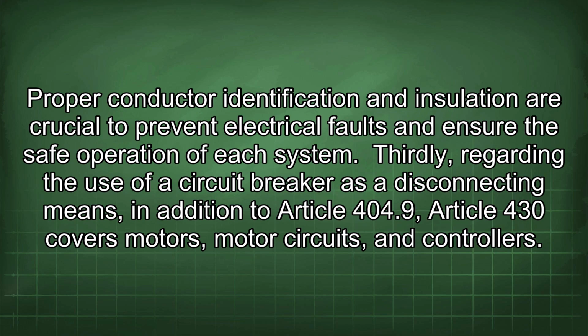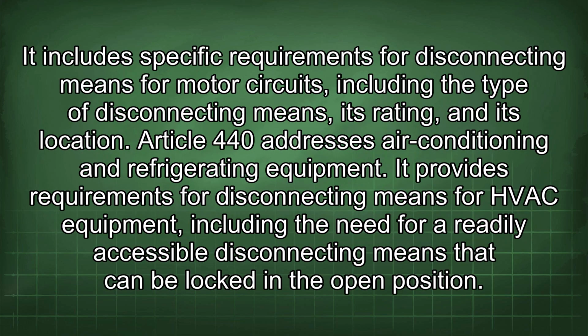Thirdly, regarding the use of a circuit breaker as a disconnecting means, in addition to Article 404.9, Article 430 covers motors, motor circuits, and controllers. It includes specific requirements for disconnecting means for motor circuits, including the type of disconnecting means, its rating, and its location. Article 440 addresses air conditioning and refrigerating equipment.